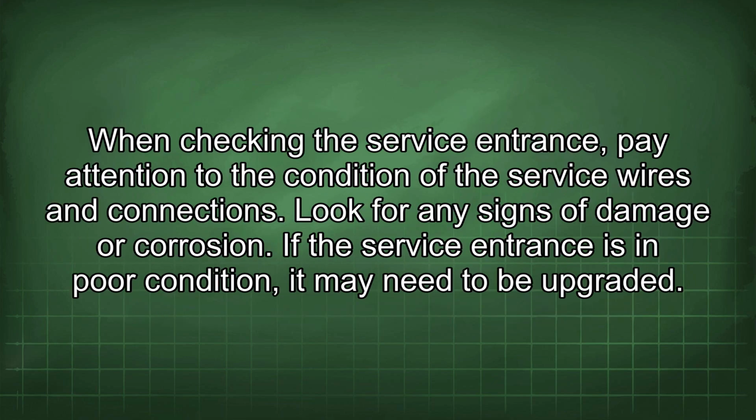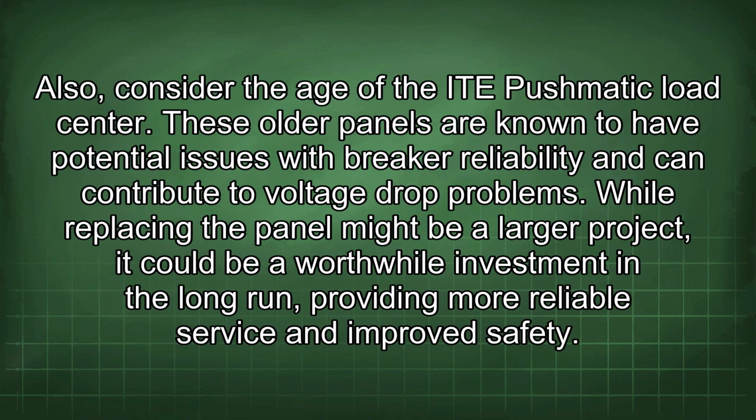When checking the service entrance, pay attention to the condition of the service wires and connections. Look for any signs of damage or corrosion. If the service entrance is in poor condition, it may need to be upgraded. Also, consider the age of the load center. These older panels are known to have potential issues with breaker reliability and can contribute to voltage drop problems. While replacing the panel might be a larger project, it could be a worthwhile investment in the long run, providing more reliable service and improved safety.